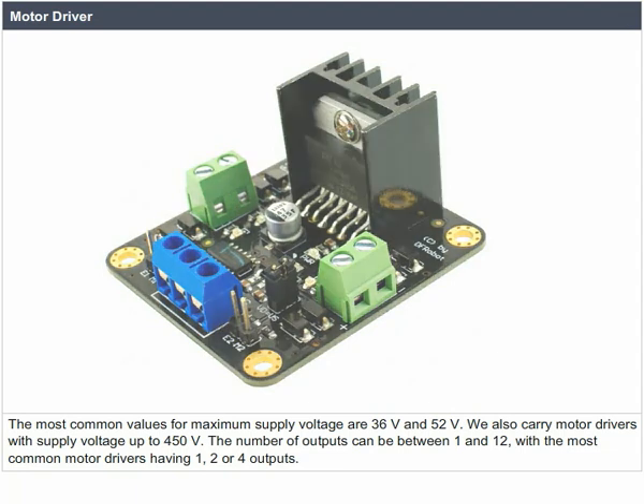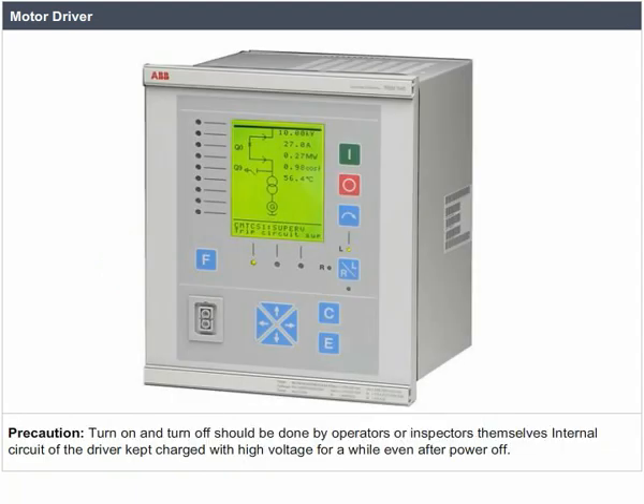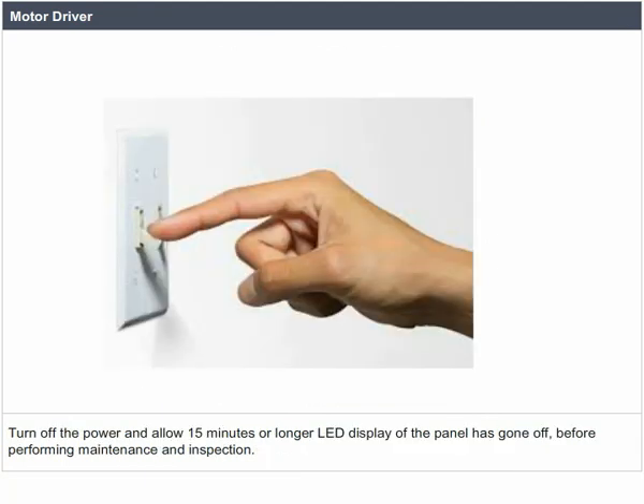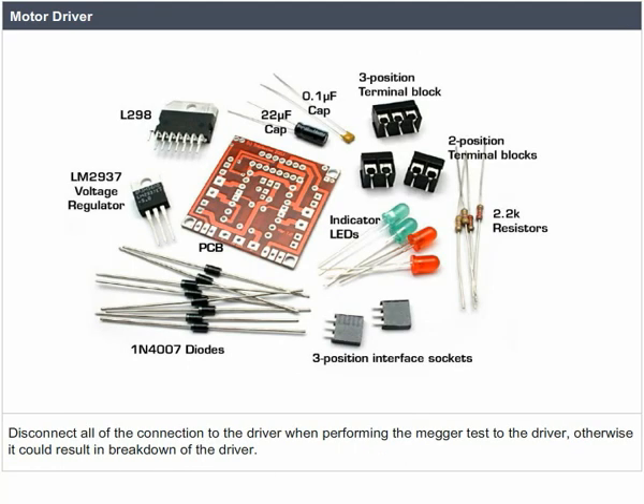Precautions. Turn on and turn off should be done by operators or inspectors themselves. The internal circuit of the driver is kept charged with high voltage for a while even after power off. Turn off the power and allow 15 minutes or longer, until the LED display of the panel has gone off, before performing maintenance and inspection. Disconnect all of the connections to the driver when performing the megger test on the driver. Otherwise, it could result in breakdown of the driver.